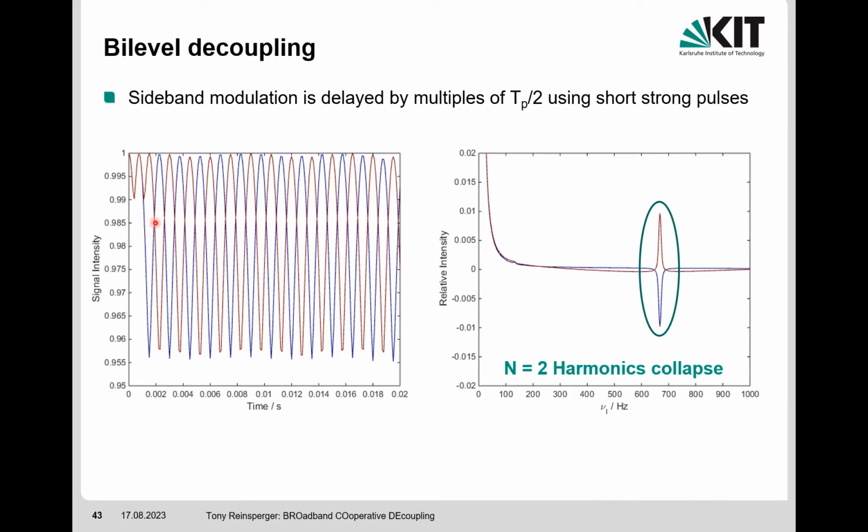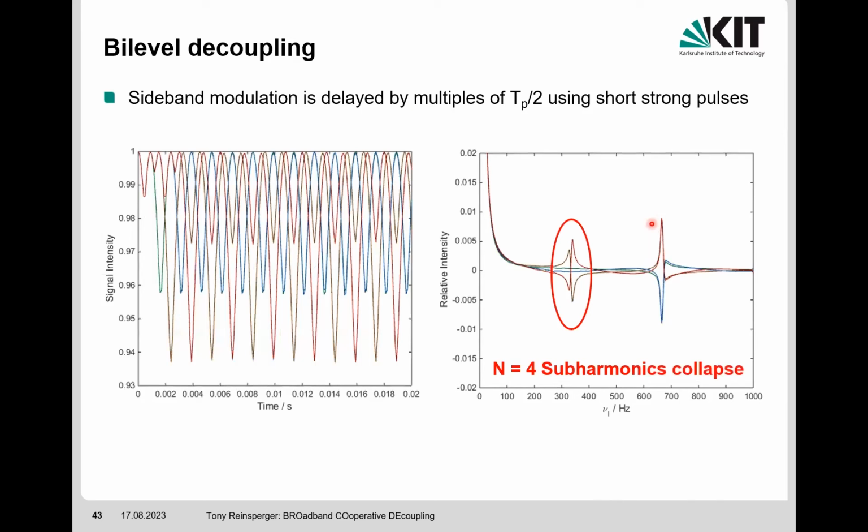So it starts delayed, this periodicity. And that leads to a phase change in the sidebands, in this case to a 180-degree phase change, which means you take 2 scans, and if you add them up, you will subtract this sideband. And if you do it for these 4 scans, then even here the subharmonic will be canceled out, while just taking half the sequence, shifted by half the pulse length, gives you only cancellation of the harmonic.